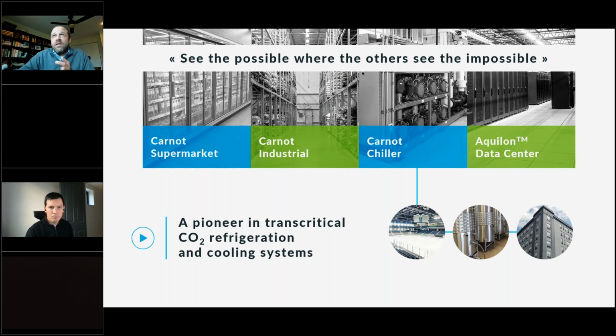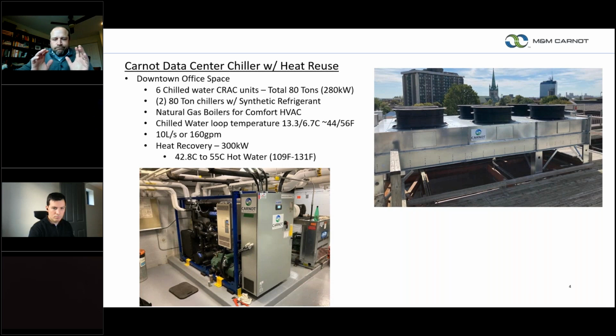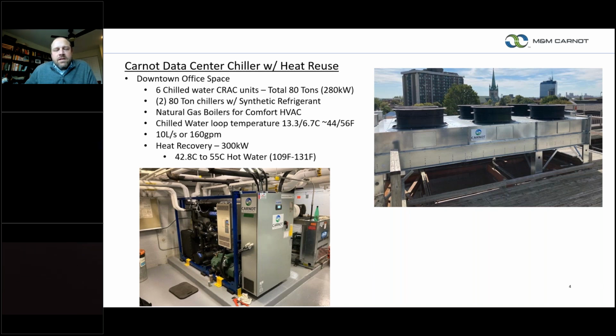But as of around 2012, we started getting into data center cooling. I'll talk a little bit about why CO2, a natural refrigerant, is a perfect refrigerant for data center cooling. But let me get right into one of our latest designs for a chiller that does heat reuse. This machine is rated around 280 kW of cooling. The room that it serves has about 6 chilled water CRAC units scattered throughout a small data center in a building that also has office space. The idea was that with CO2 refrigerant, we could provide the cooling for those 6 units at 80 tons, and then move that heat into a building hot water loop to provide heating for that building.